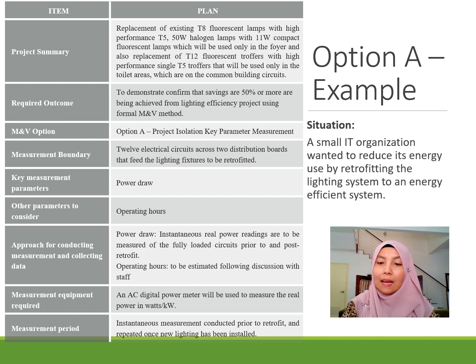Okay, these are the results of the measurement. So you can see the power draw measured at each of the circuits from DB1 and DB2. This is the measured baseline power draw, and this column shows the measured reporting power draw, and this column is the operating hours stipulated with the staff in the building, and these four columns show the calculation of energy and the energy saving. As you may know, energy is equal to the power draw times the operating hours. So we get this baseline energy, and this post retrofit energy is the reporting power draw multiplied with the same operating hours. Then we will get the post retrofit energy.